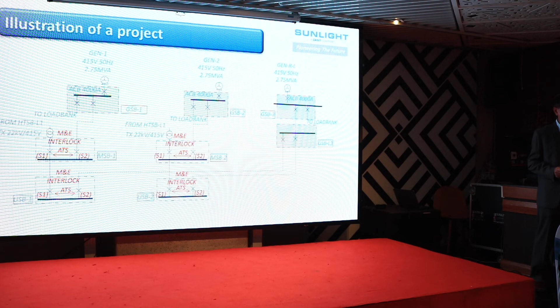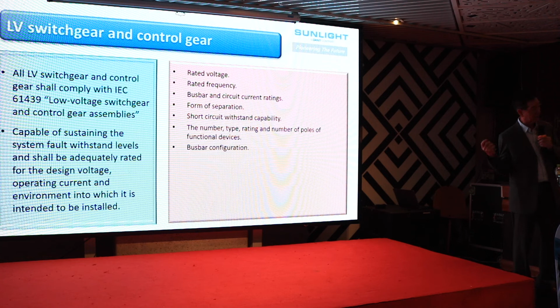Capable of sustaining fault withstand. That's very important because we say for tier 4, it has to be fault tolerant. Adequately rated for the design voltage, operating current, and the environment it is intended to be installed in. These are all quite common parameters that you need to see and specify, or the solution provider, the panel builder for example, will have to take all this into consideration.